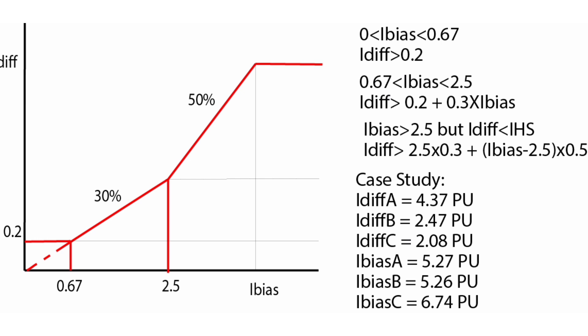Here the differential current for phase A, phase B, and phase C are 4.37 per unit, 2.47 per unit, and 2.08 per unit respectively. And bias current for phase A, phase B, and phase C are respectively 5.27 per unit, 5.26 per unit, and 6.74 per unit.